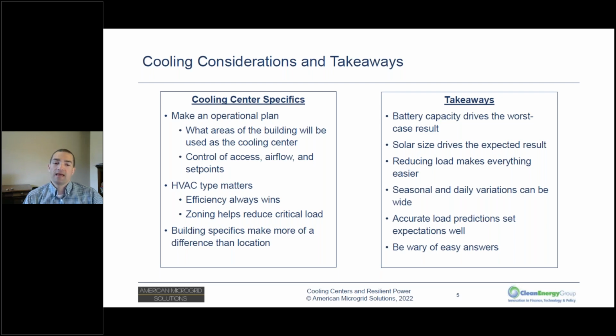That may be less efficient if you're only trying to support part of the building, depending on how you can do zoning, than the other end of the spectrum, like our West Coast site, which happens to be Nikki's site out at CIMCC. At that facility, there are multiple rooftop units, each with its own zone, individually controlled. So if we just turn off all the ones in the parts of the building we're not using, that's a zero on electricity use for those, instead of some of the inefficiency left over from using one large system to supply the whole building.